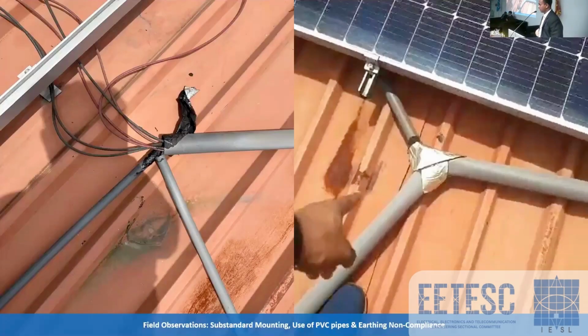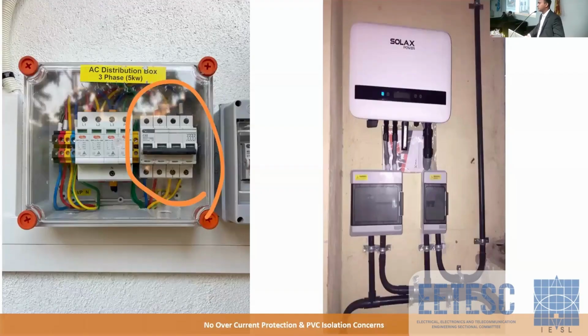And this is also kind of an insulation issue. This may cause a lot of insulation issues, even fire issues. These insulations are made with PVC and some no-leak tapes. This kind of installation we have seen in some places. I'm not talking about all.